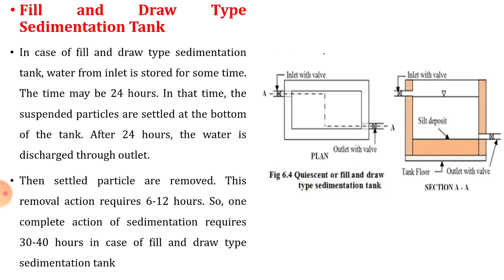The time may be 24 hours. In that time, the suspended particles are settled at the bottom of the tank. After 24 hours, the water is discharged through the outlet. Usually, as shown in the figure, the inlet is provided at the top of the tank whereas the outlet is provided at the bottom after providing sufficient depth for the deposition of silt or suspended particles. Then settled particles are removed. This removal action requires 6 to 12 hours. So one complete action of sedimentation requires 30 to 40 hours in case of fill and draw type.